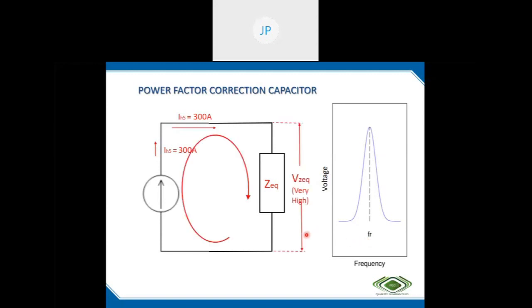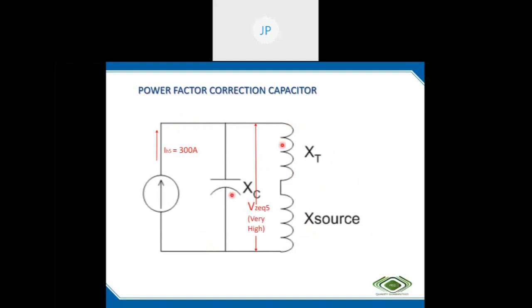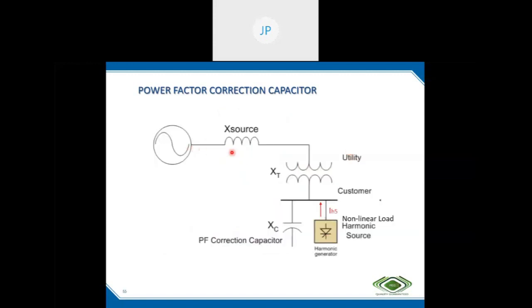This increased voltage is available across both circuits, and both impedances are the same but in opposite directions. So a current will flow through this branch, and in the opposite direction it will flow in this direction. So a very high current will circulate within this. This is the resonance current. It is very much higher than the actual harmonic, which means the harmonic is amplified very highly. This harmonic is injected into the source, so this high current will be injected into the source. Totally amplified harmonics.